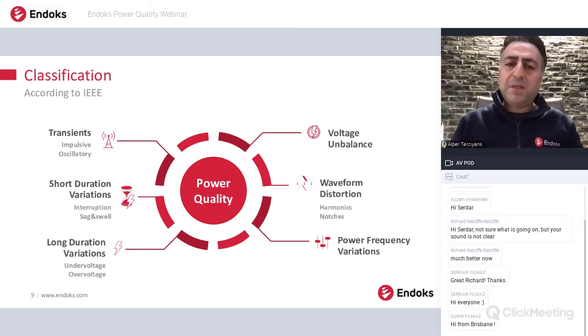Voltage imbalance is also another problem. Mainly on the low voltage side we observe voltage imbalance, and on the medium voltage side we see these imbalances mostly with special industrial loads like arc furnaces and single phase loads like railway applications. It is very important to avoid imbalance, because in a low voltage network, imbalance creates neutral conductor currents. These can lead to a voltage difference between the neutral and the earth potential, which might affect devices like monitoring devices in hospitals or IT equipment. So voltage imbalance, especially on the low voltage network, should be avoided.